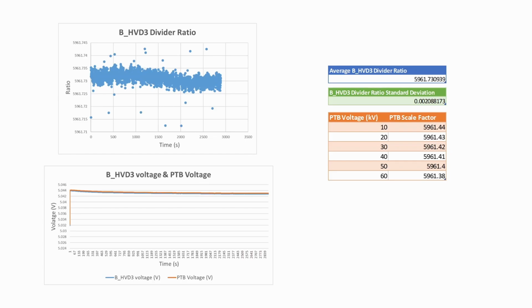And we compared it, now we needed something to compare it to because our old divider wasn't working, so we need something to compare the new divider against to see if it's working properly, like a divider that has already been calibrated and already functions as intended. So we ordered a high voltage divider from the Metrology Institute of the Federal Republic of Germany. That is the PTB voltage you see in the second graph. And we can see that both of the graphs are pretty much in alignment. So the high voltage divider that we built performs well and is in line with the performance of the reference divider. Therefore, it is effective for use in our experiments.